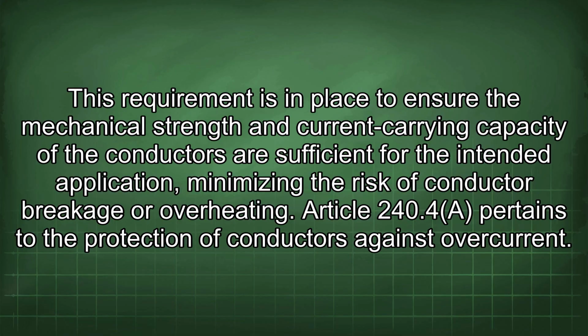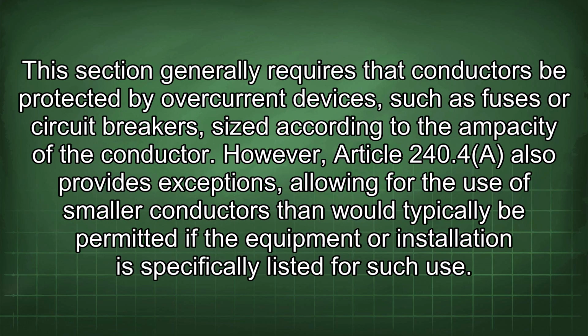Article 240.4 pertains to the protection of conductors against overcurrent. This section generally requires that conductors be protected by overcurrent devices, such as fuses or circuit breakers, sized according to the ampacity of the conductor. However, Article 240.4 also provides exceptions, allowing for the use of smaller conductors than would typically be permitted if the equipment or installation is specifically listed for such use.